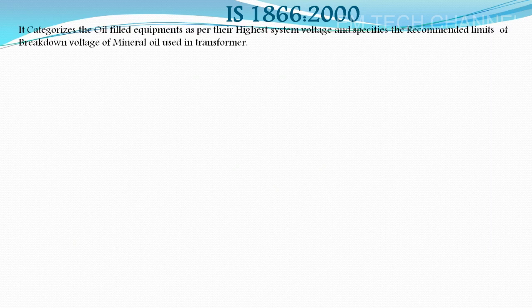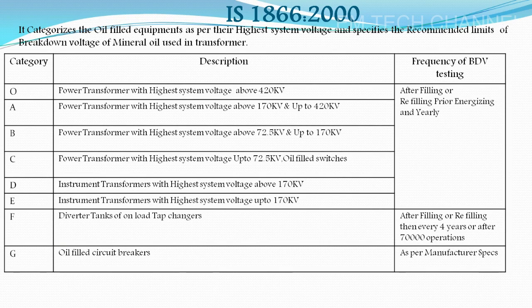This IS 1866-2000 categorizes oil-filled equipment into 8 categories as per their highest system voltage and specifies the recommended limits of the breakdown voltage of mineral oil used in the transformer. You can see here from O to G. Power transformers with the highest system voltage above 420 kV fall in the O category, and power transformers with highest system voltage above 170 kV and up to 420 kV fall in the A category. Power transformers with highest system voltage above 72.5 kV and up to 170 kV fall in the B category, and power transformers with the highest system voltage up to 72.5 kV and oil filled switches fall in the C category.